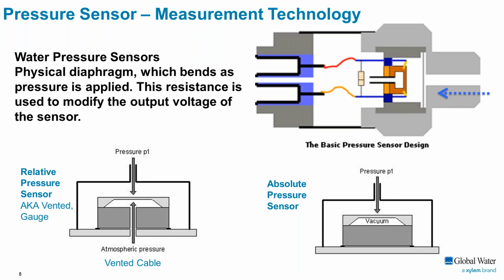So as we come in from the right, you can see the little arrow comes in. Water pressure penetrates through the little channel of the submersible pressure transmitter. It gets up in the center where, on the WL400, the manufactured sensor, it has a silicone diaphragm, which acts as a balloon. As water pressure comes in, it pushes against the diaphragm, which then sends an electrical signal through some resistors to our logic board, and then it produces a 4 to 20 milliamp signal based on the type of diaphragm that we've positioned in there and the configuration we put onto our logic boards.